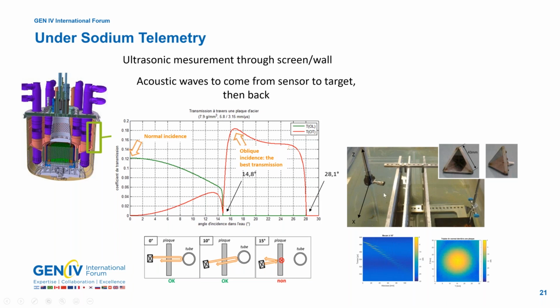What you see on the right are some test devices with the sensor on the left, some plates immersed in water, and some very specific target, which we call a three-plane target, which in fact is a corner of a cube. If you cut a corner of a cube, you will have such a target with the three planes being orthogonal from the others. And using that target, we know that it is the best target in order to get an echo, as the drawback of that method from the outside is that when crossing the interfaces between stainless steel structures of the main vessel or immersed components and liquid sodium, of course, the energy is decreasing very fast.